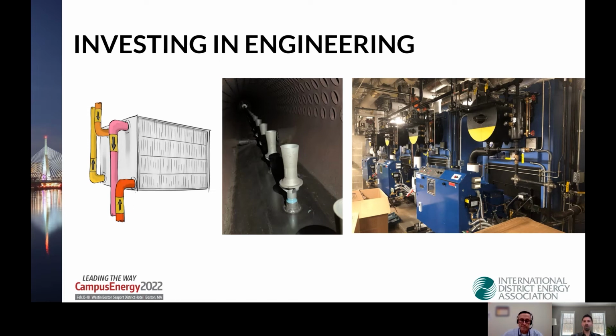Some ideas on the screen are examples of what we proposed to Brown. On the left, as David mentioned, we had to convert many ventilation systems and air handling units, sometimes 100% fresh air units. We had to replace the coil anyway to convert from steam to hot water. But while doing this disruption, there's also an opportunity to perform a heat recovery system, because if you've got a 100% fresh air system, you've also got the exhaust.